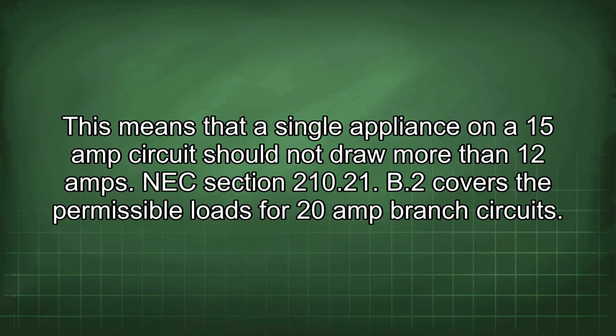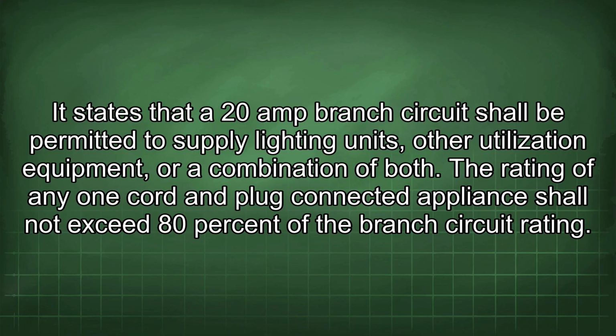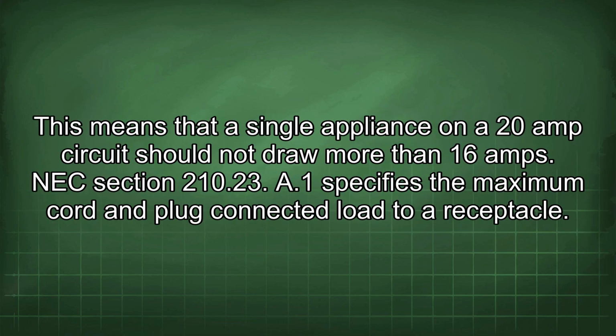NEC Section 210.21(B)(2) covers the permissible loads for 20 amp branch circuits. It states that a 20 amp branch circuit shall be permitted to supply lighting units, other utilization equipment, or a combination of both. The rating of any one cord and plug connected appliance shall not exceed 80% of the branch circuit rating. This means that a single appliance on a 20 amp circuit should not draw more than 16 amps.